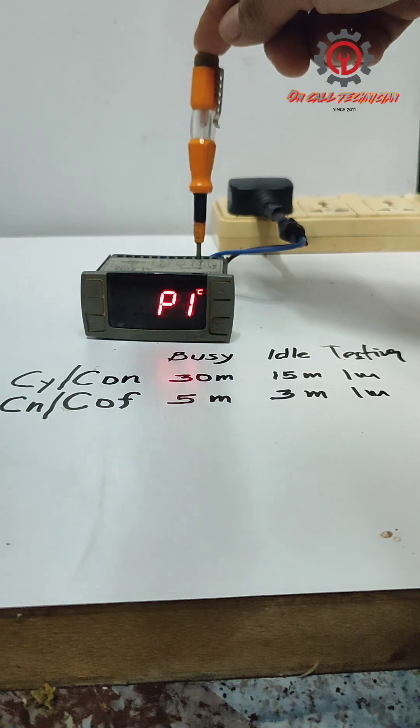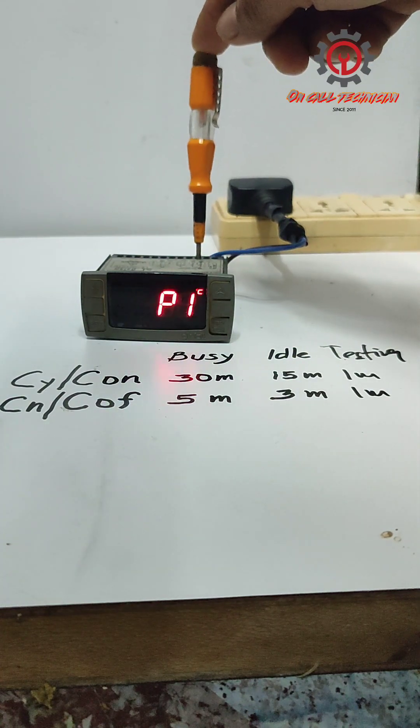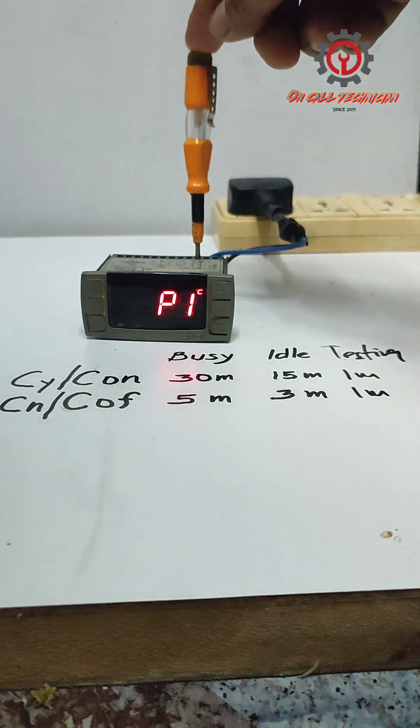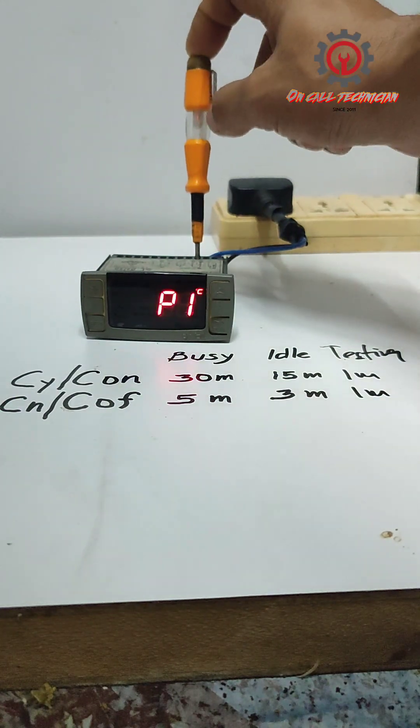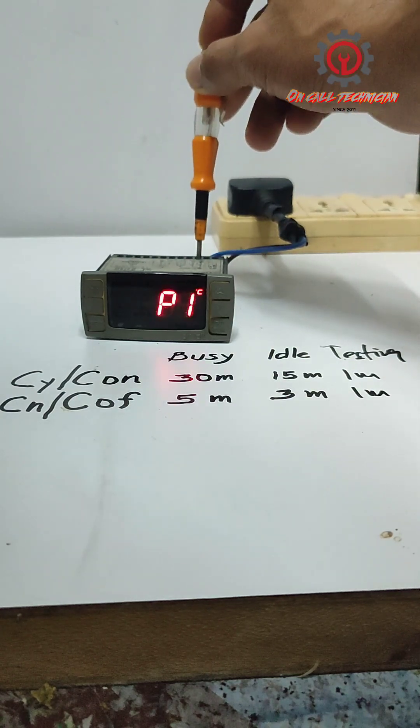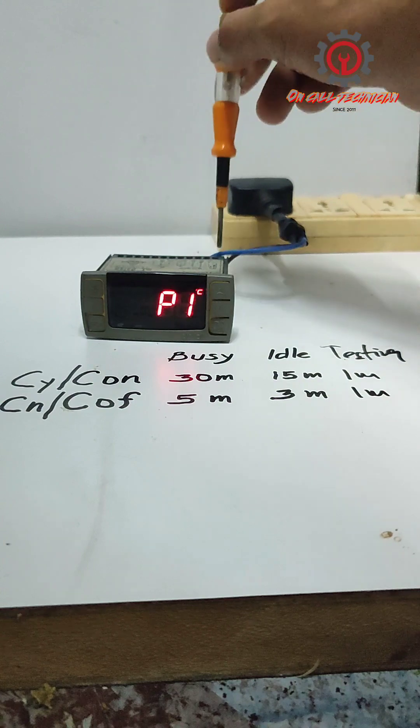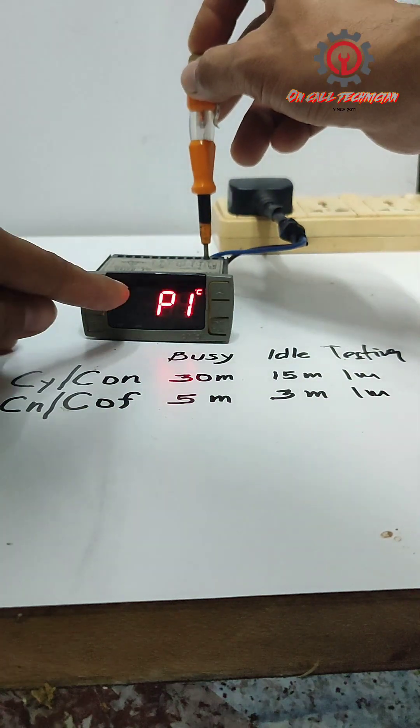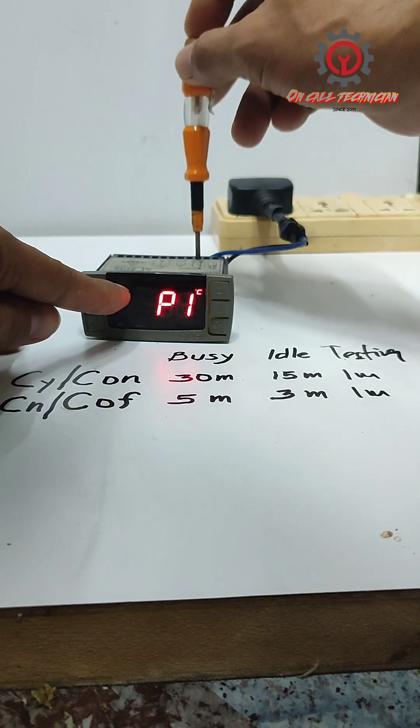So CN cut off, it will cut in at one minute. My test pen is on terminal number three proving the compressor and the fan motor is off and the symbol here is being gone.